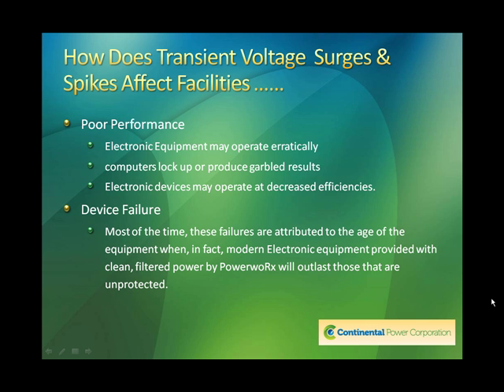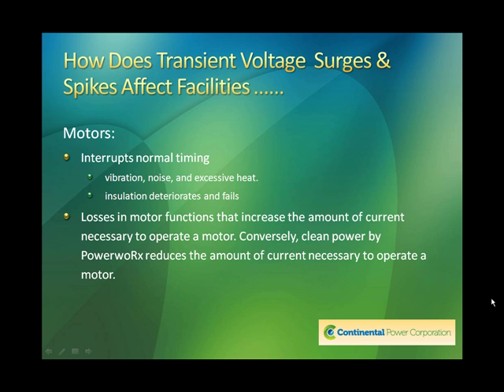Transient voltage surges and spikes affect facilities in many ways. First of all, poor performance. Electronic equipment can operate erratically. Computers lock up or you lose data, produce garbled results. Electronic devices may operate at decreased efficiencies. You get flat-out device failure. Most of the time we attribute these failures to old age of equipment, but if that equipment had the protection of the PowerWorx unit on it, it would outlast those that are unprotected. There's no question about that, because electronic components may not fail immediately, but you have latent damage, and that latent damage over time will add up and cause premature failure. How do spikes affect facilities in other ways? Well, motors is a big one.